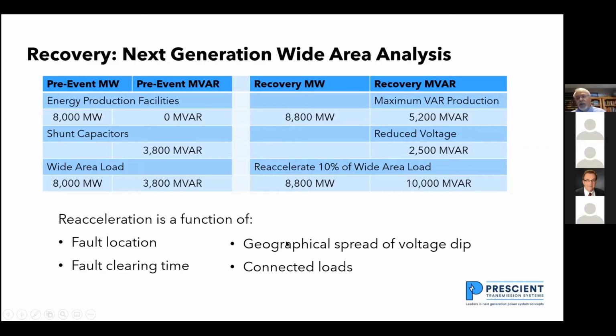The geographical spread of the voltage dip: I have to plot voltages over a geographical map of the area so that I can get an understanding of what's going to reaccelerate. And fault clearing time is important. 100 milliseconds is typical clearing time for three-phase faults on high voltage systems, and the reason 100 milliseconds is key is that's a couple of revolutions of a 1200 RPM motor. So you want to know the connected loads. Are they air conditioners or fans? And you want to know what the fault clearing time is.